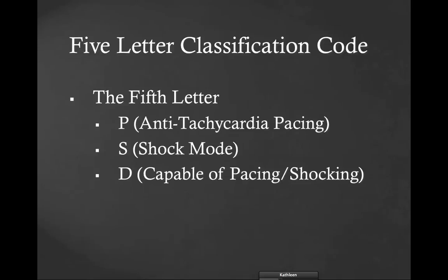Now remember, some patients are not in sinus arrest or in bradycardia all the time. So they only need that pacemaker to work when they're symptomatic. So the pacemaker will inhibit, meaning it won't allow the pacemaker to work. It will inhibit the pacemaker from working if it senses the patient's own beat is above the set rate. So for example, if I had a pacemaker and my pacemaker was set at 60 and the electrodes, both in my atria and ventricles, are sensing that my heart rate's 64, then it's going to inhibit the pacemaker from working and let my heart beat on its own.